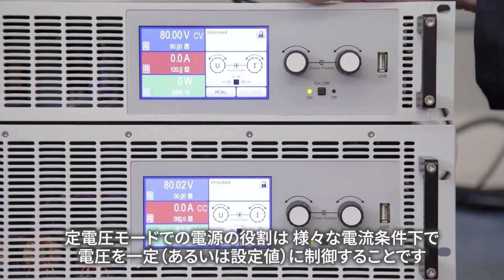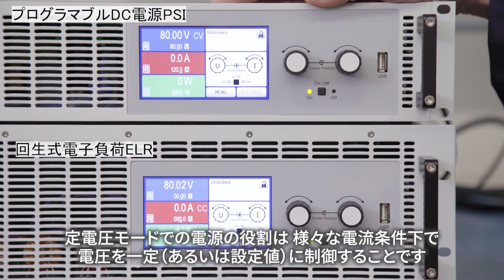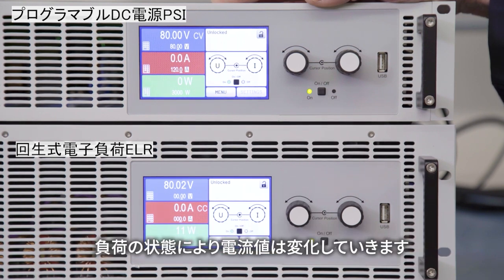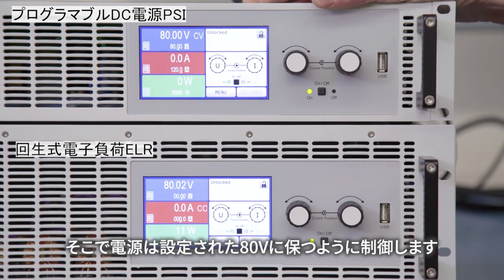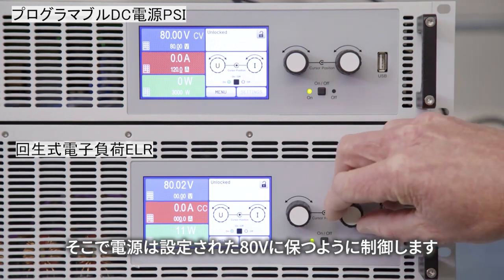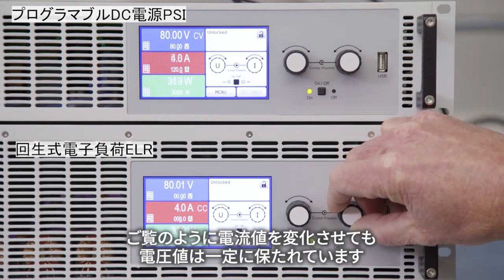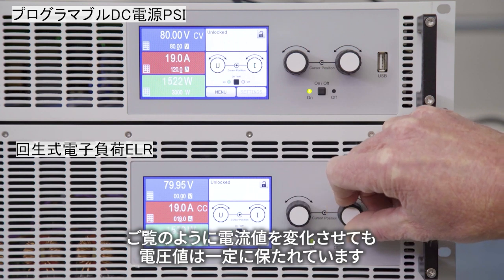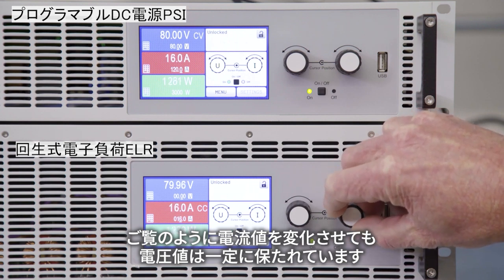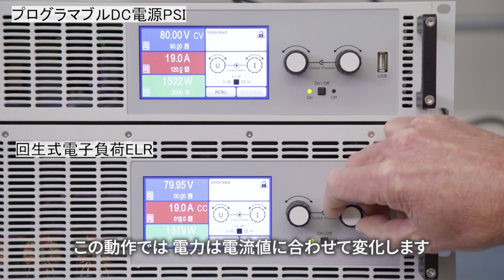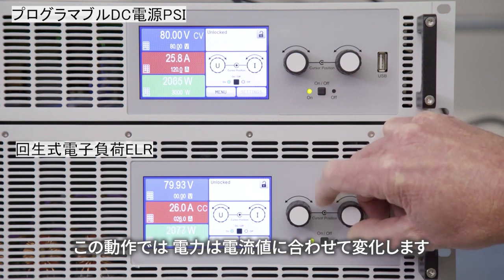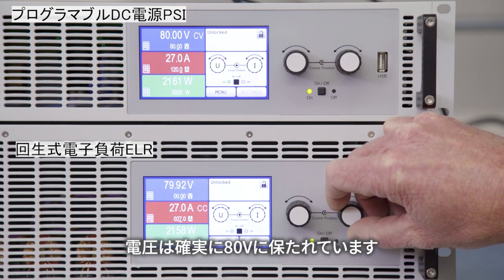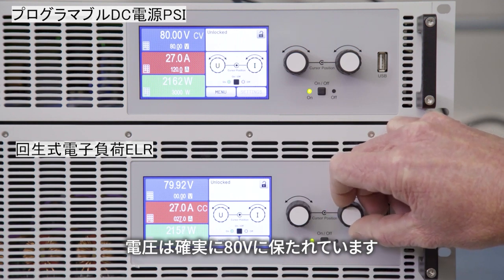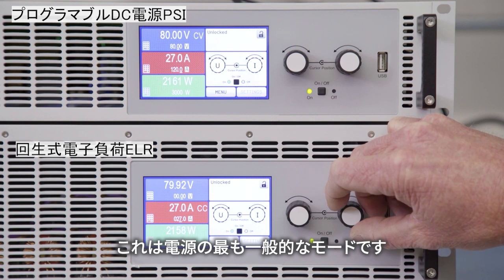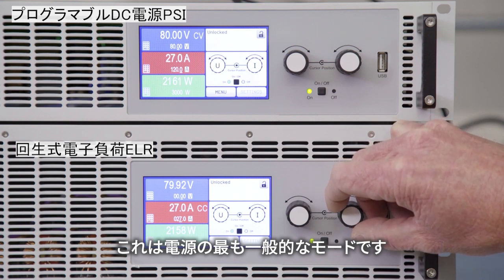In constant voltage mode, the power supply's job is to maintain a constant voltage on the output independent of the current. If your load has fluctuating current levels, the power supply is going to sit there and maintain the 80 volts that you've programmed. You can see as we fluctuate the current, the voltage actually stays the same. In this mode, you'll see the power alternating as a function of the current, yet the voltage is maintaining exactly at 80 volts. This is probably the most common mode of operation for power supplies.